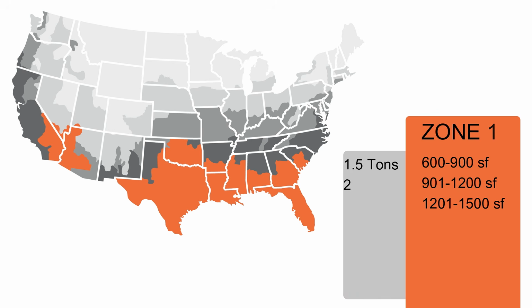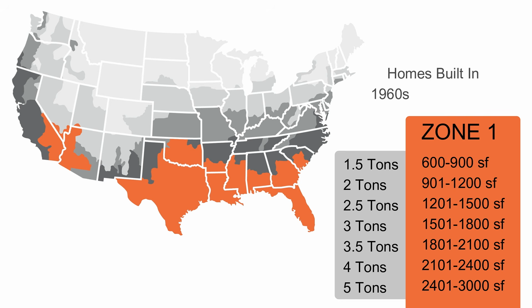So if you're looking at the chart, you're going to see that there's a range in square footages for particular size of tonnage. And I would recommend, if you have a house that was built in this time frame, I would lean more on the smaller square footage side of the equation, and it's typically going to be more correct than not. If you have a 1,500 square foot home, I would go with a 3-ton system. If you have an 1,800 square foot home, I would go with a 3.5 ton system. And again, this is still just a rule of thumb.